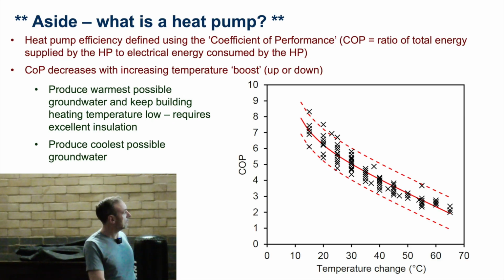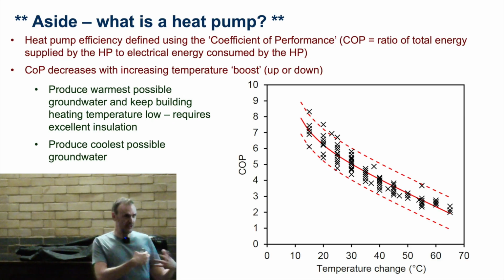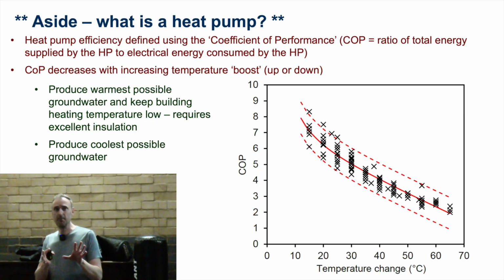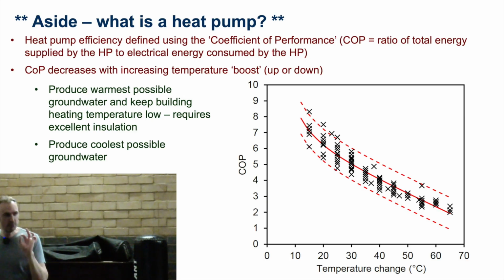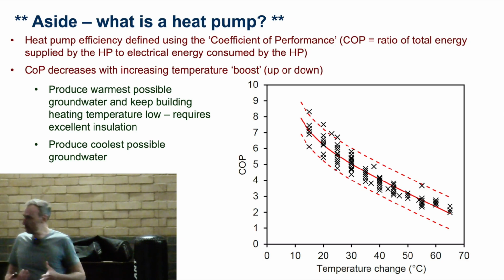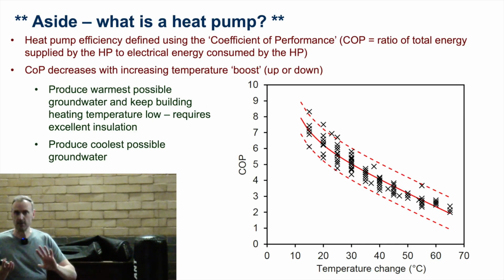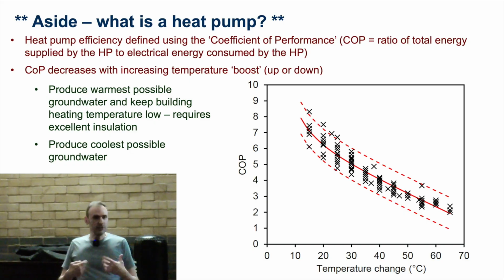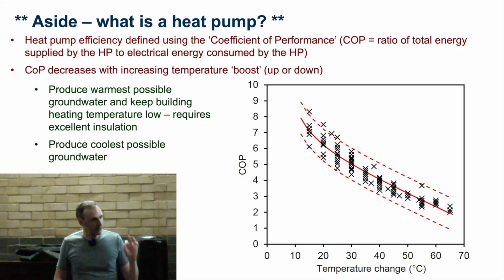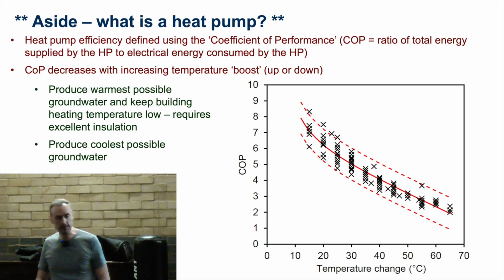So from the geothermal side — I'm not a heat pump person — what that means is I need to produce groundwater at the highest possible temperature for heating and the lowest possible temperature for cooling, to make the heat pump as efficient as possible. That's my job as the geothermal person, and it's the building service engineer's job to make the heat pump work properly. So that's a constraint on me: get that groundwater out as warm as possible, or as cool as possible.